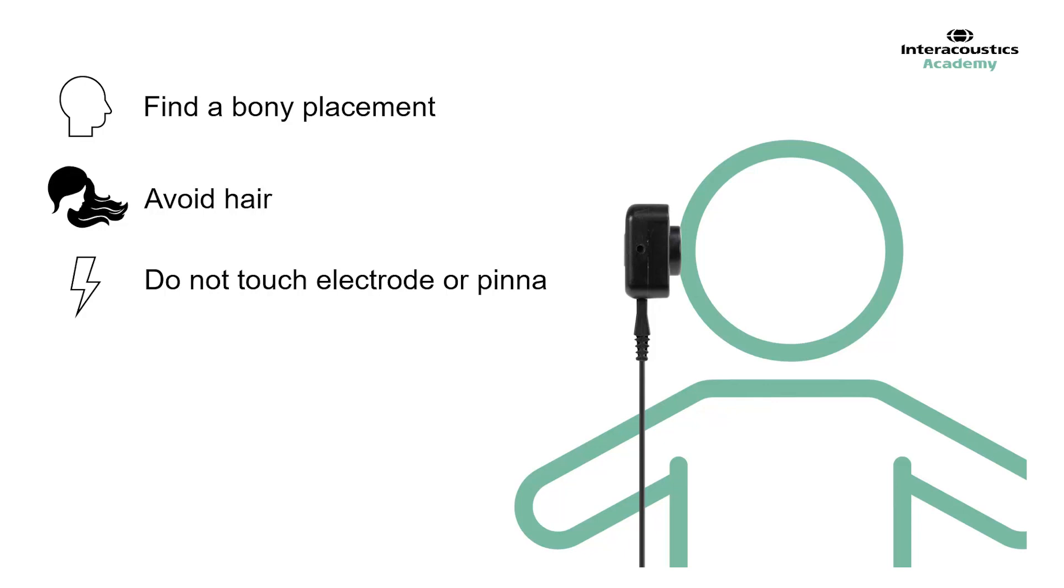Ensure that the bone conductor does not touch the electrode or the pinna as this can introduce stimulus artifact. It can help to use a separate finger to hold the pinna out of the way. Ideally, you want at least a finger's width between the electrode and the bone conductor.